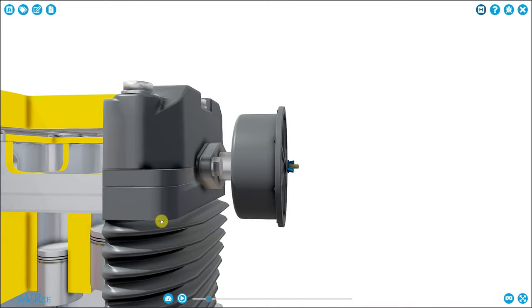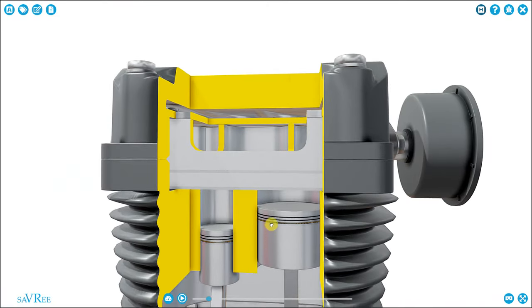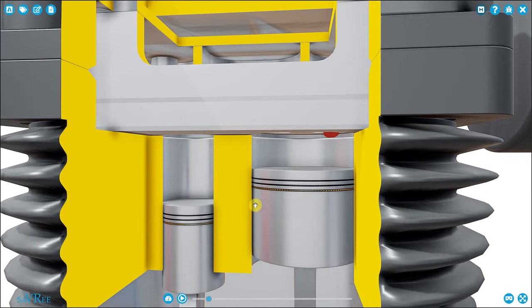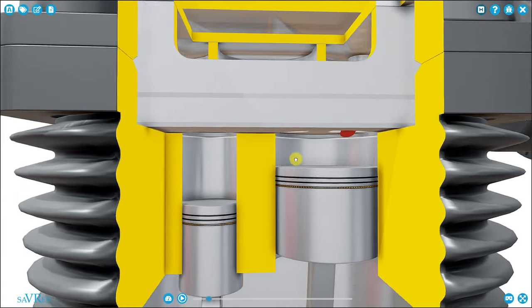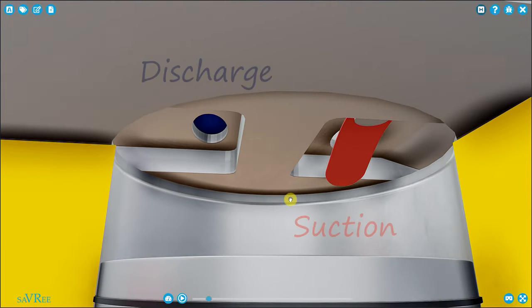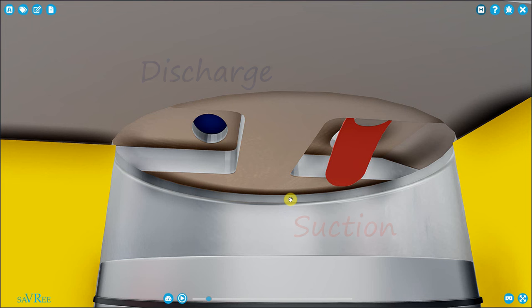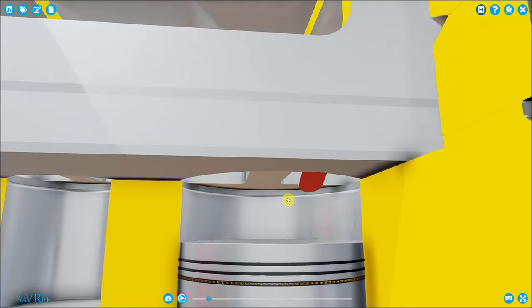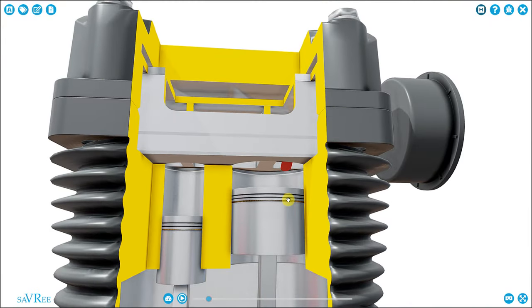Ultimately, we're protecting the internal components from damage — not just the piston and the cylinder liner, but also the valves, which are located at the top of the cylinder. We've got a red one and a blue one. These are our suction and discharge valves. These are very basic — they don't actually look like this, but showing the valves like this makes it easier to understand exactly what's going on in the compressor. It's these valves that we're trying to protect when we filter out the grit, the sand, the dirt, and other foreign particles from the air coming into the air compressor.